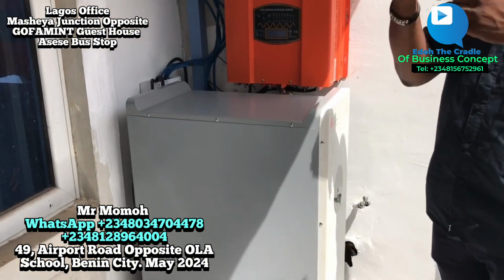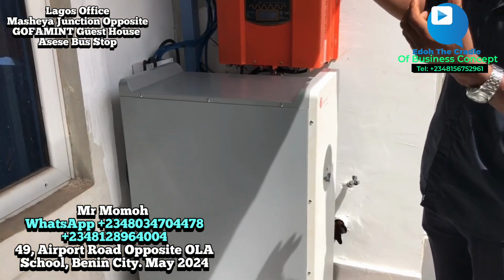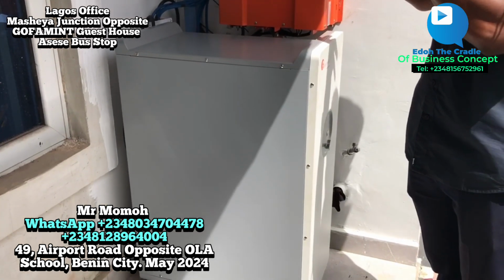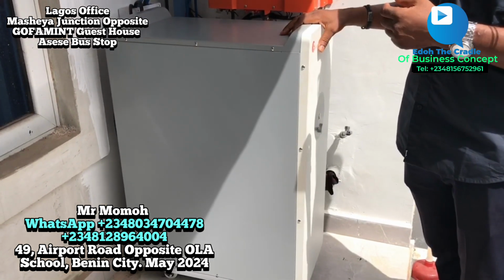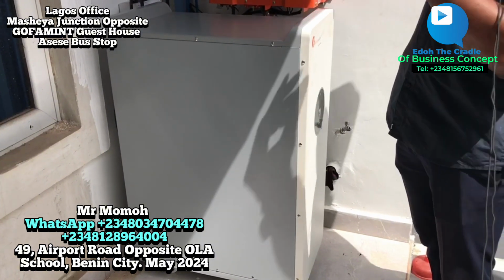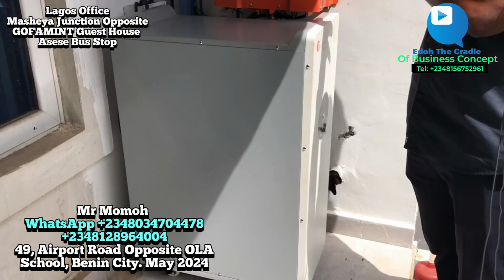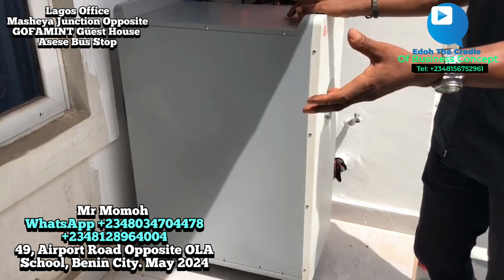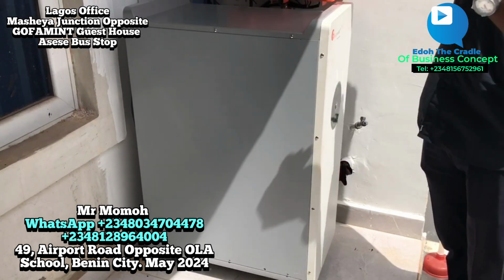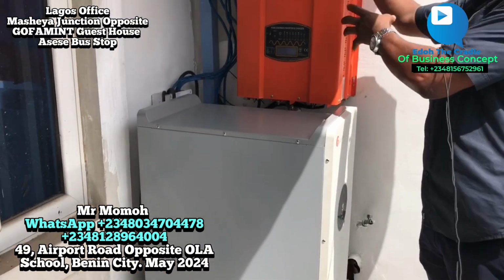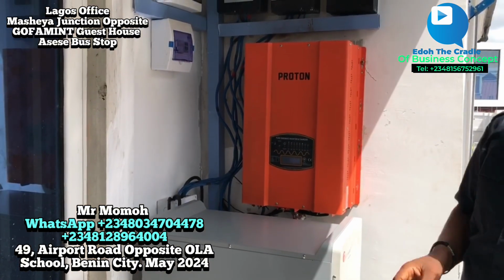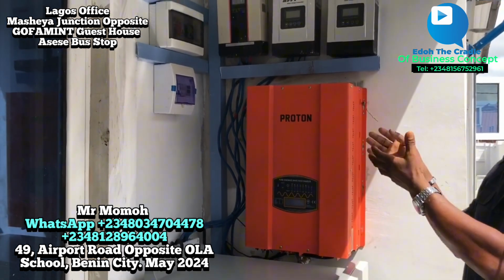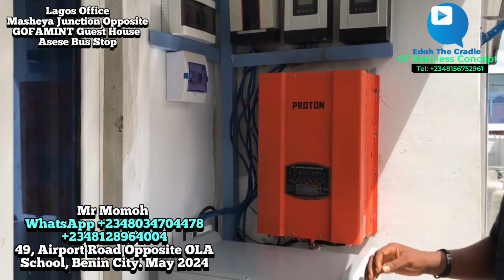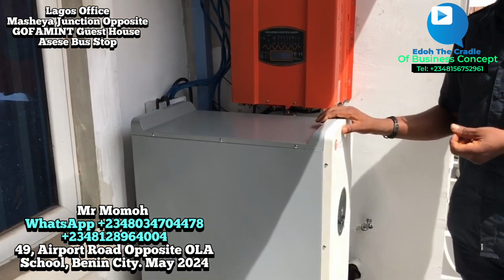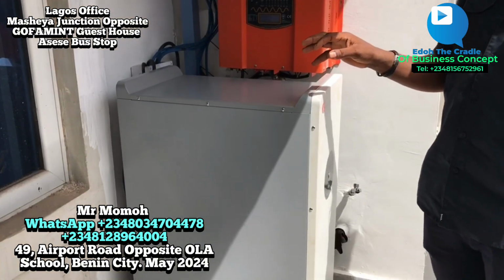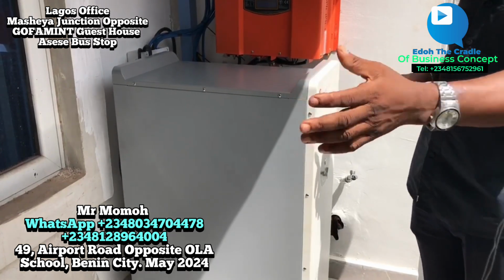That collides with the advice I try to give people: don't bring in a 5 kVA or 10 kVA inverter to power a 15 kilowatt lithium battery. It is a very wrong installation. Or don't bring in 10 kVA or 5 kVA to power a 4-battery system, the tubular type. The reason is that when you put on loads the inverter can carry, that battery does not have the power to carry the same load. So why go for an inverter that will carry an overload the battery cannot carry? Then you are killing the battery, whether lithium or tubular. That's why it's not advisable to use 5 kVA to carry a 15 kilowatt lithium or a 4-battery tubular system.